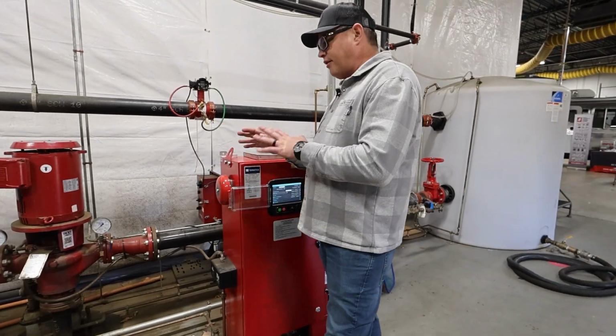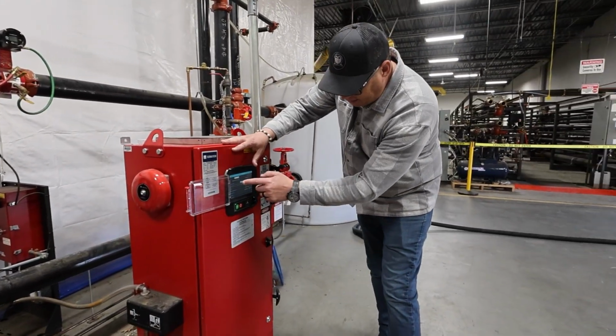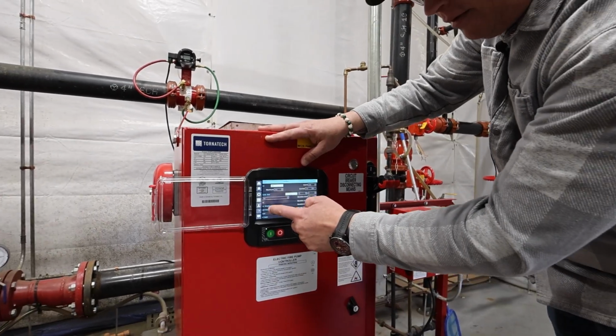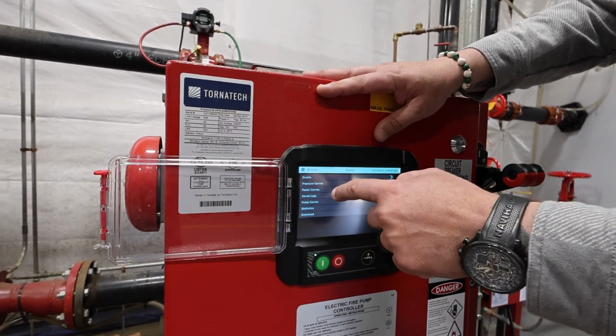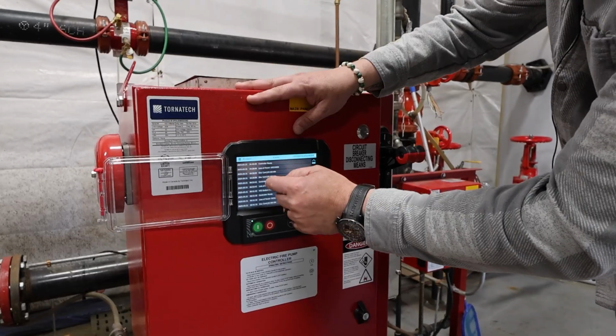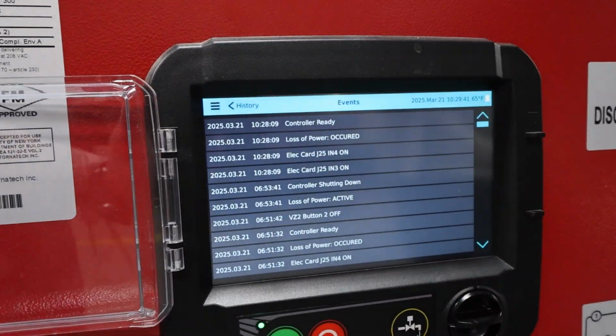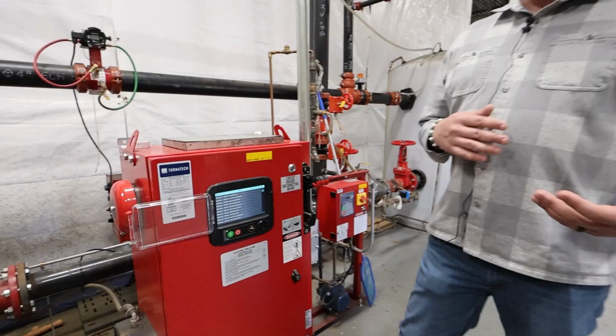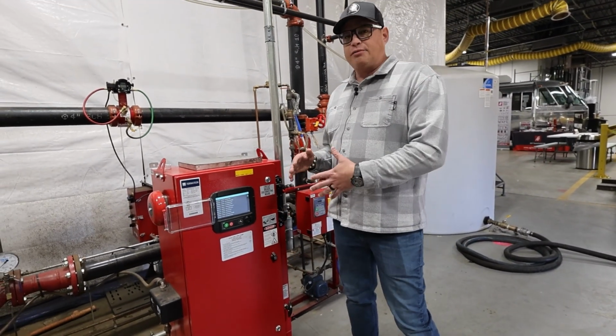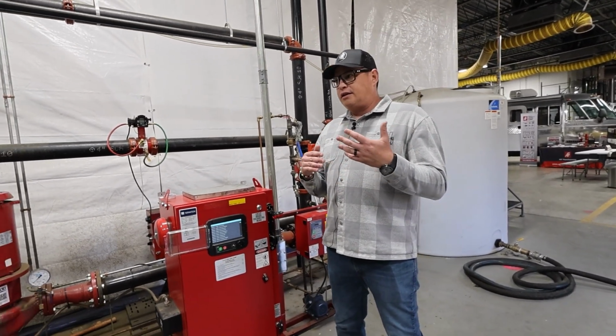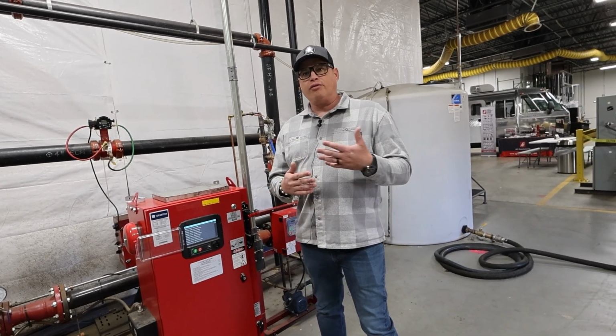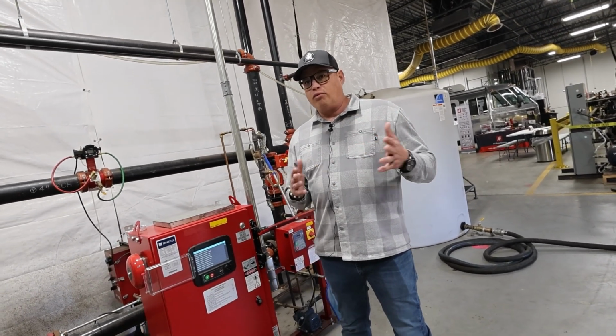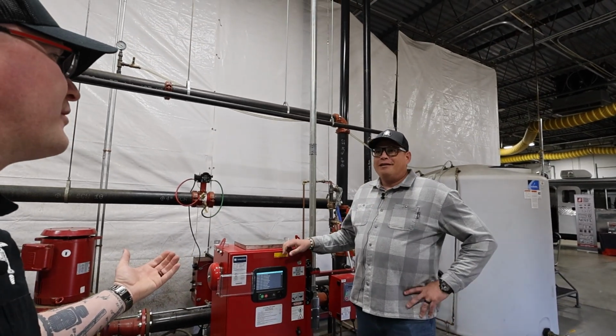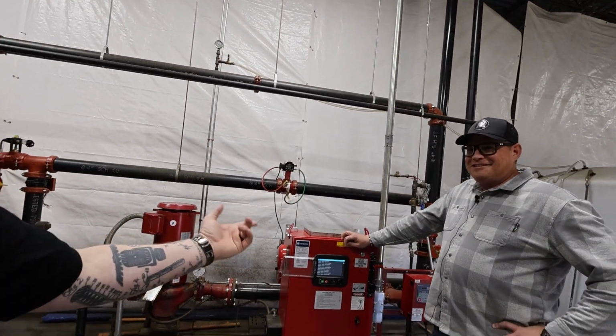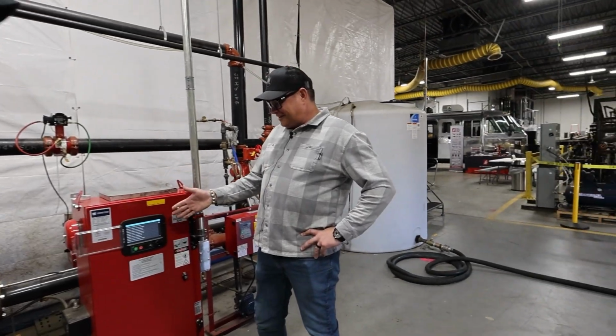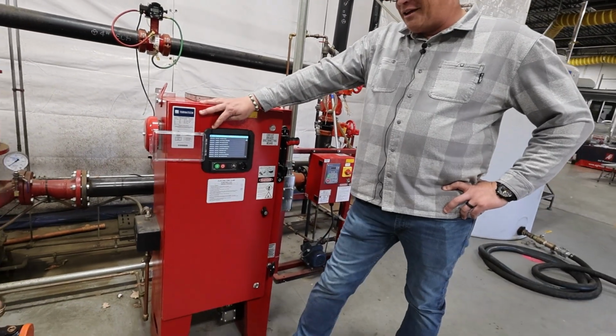Now, say we've gone through everything else, I'm also gonna go back here into my log, and me personally, I'm gonna download all of the events that have happened with this controller, which will show me every time it's been run. And the reason I wanna do that is, this is a new customer for me. We're doing their run test now, but did the previous inspector do all the run tests as they should? And then we would know. Yeah, of course they did. They've got the paperwork to prove it. Yeah, right. You were talking about that in your presentation. You call this the lie detector. That's right. This is the fire pump lie detector. It will tell you everything.